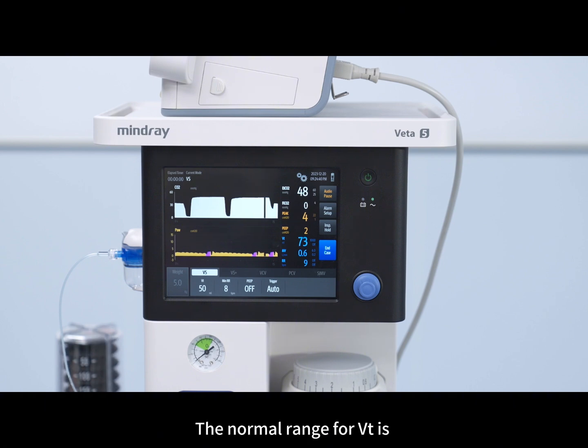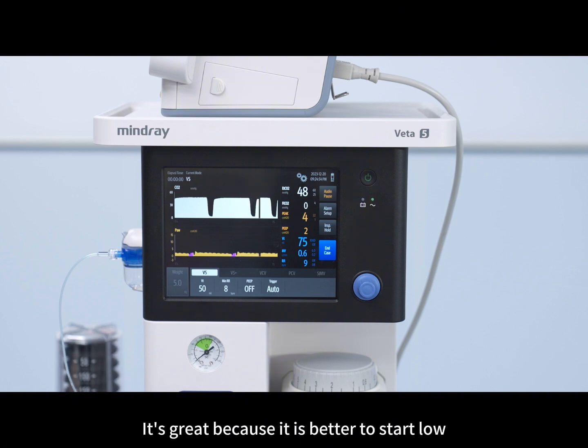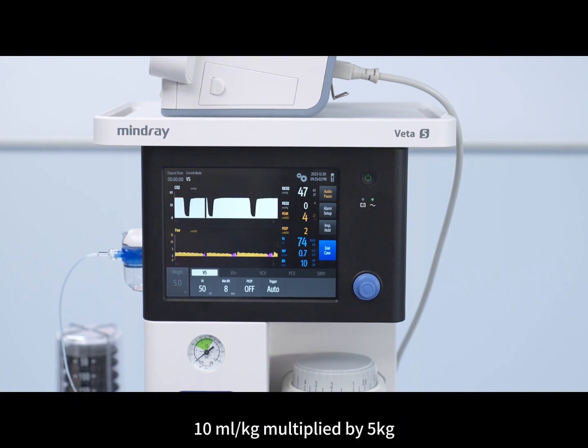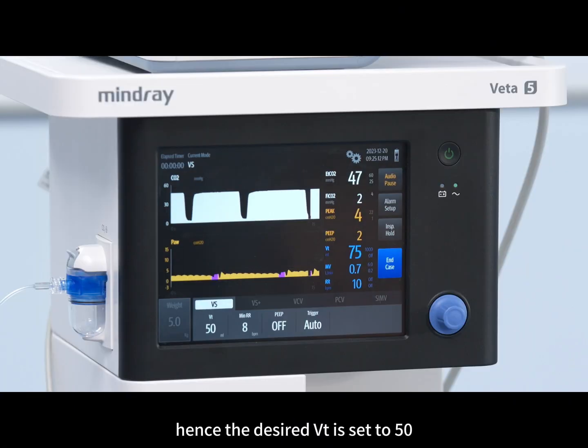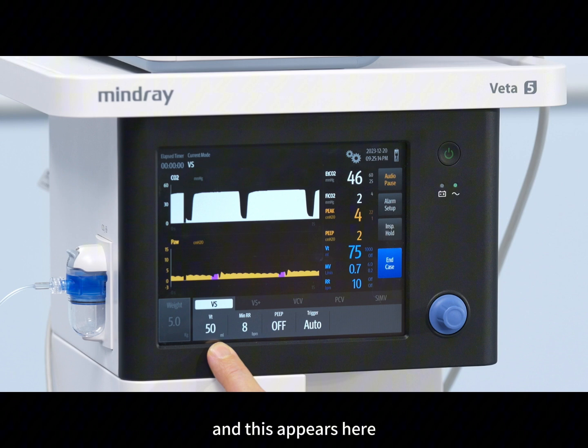The normal range for a tidal volume is 10 to 15 milliliter per kilo of lean body weight for healthy small animals. The default tidal volume calculation of Veta 5 is rather conservative, as it starts at the low end. It's great because it's better to start low and increase it later on if needed. In this case, the tidal volume is 10 milliliter per kilogram multiplied by 5 kg, which is 50 milliliter. Hence, the desired tidal volume is set to 50, and this appears here.